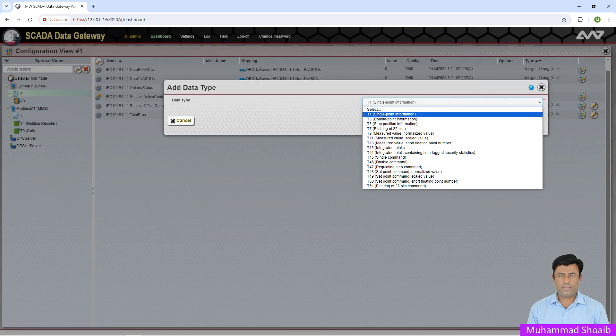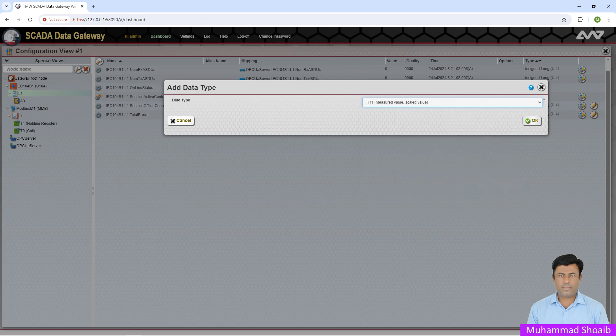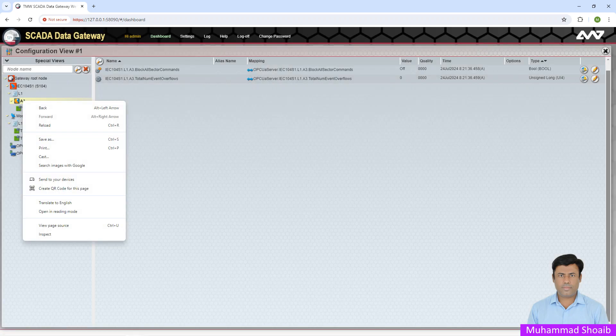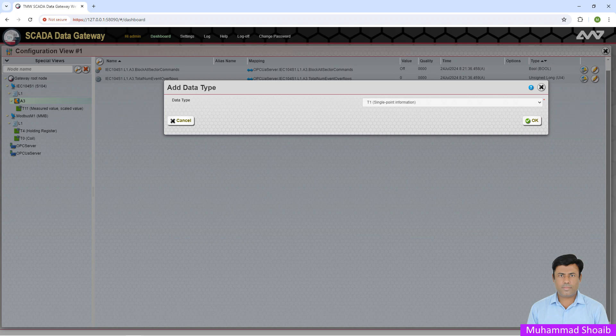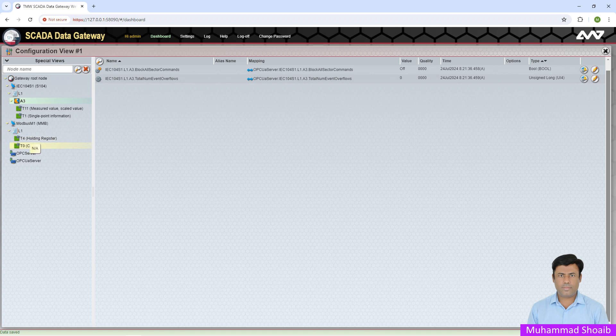Now select the data type. For my case it's measured value, so I will select 'Measured Value' and press OK. I will also add one more data type for my digital values — I'll use T1, the Single Point Information Object. Press OK. The IEC 104 server side configuration is completed, and now we'll move to the mapping step.